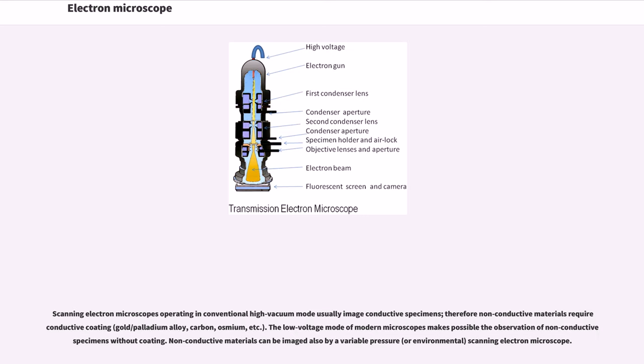Scanning electron microscopes operating in conventional high vacuum mode usually image conductive specimens, therefore non-conductive materials require conductive coating, gold-palladium alloy, carbon, osmium, etc. The low voltage mode of modern microscopes makes possible the observation of non-conductive specimens without coating. Non-conductive materials can be imaged also by a variable pressure, or environmental, scanning electron microscope.